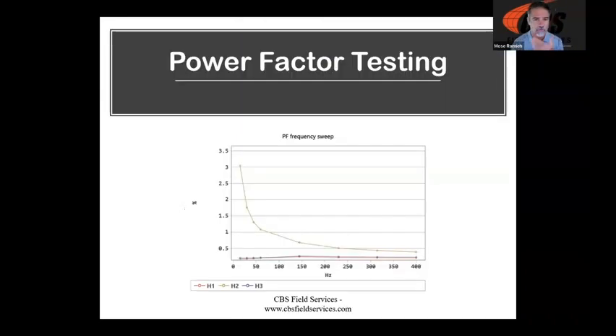So moving through those, power factor testing. Here's a great example of a bushing that we tested just the other week. And I'm so glad we had this information because we tested for a variety of frequencies. We can see H1 and H3 way down here at 0.25 or thereabouts, nice and flat and perfectly together. We'll notice that H2 has this little curve going on. Now, it's bad at 60 Hertz. It's at 1.2 at 60 Hertz. So it's already bad, but we can see just a little bit more information about it in this response that we're getting. So once again, in transformer testing, bushings in particular are one of your higher components of failure in a substation. So something to keep in mind.